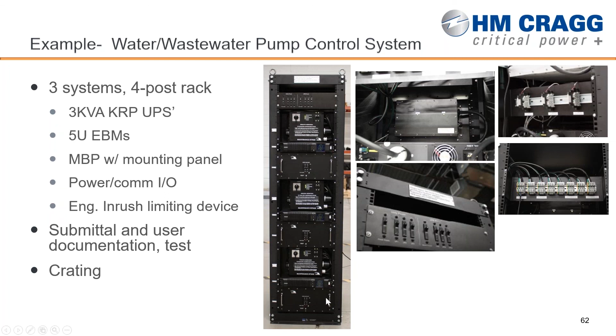This was a Falcon system that we ended up using in a high temperature pump control station overseas. We went with Falcon because they needed up to 65 C and wanted a very small footprint. So we ended up with 3 kVA UPSs, 3 maintenance bypasses, 3 5U EBMs, and a custom power distribution panel at the top, all in one 42U rack. It wasn't overly complicated, but it was interesting in form, I guess.